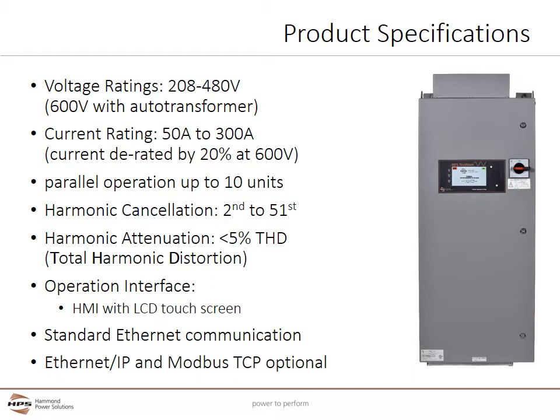The HPS TrueWave active harmonic filter offers voltage ratings from 208 to 480 volts; 600 volts can be achieved with the addition of an auto transformer. Current rating includes frame sizes from 50 to 300 amps, and up to 10 units can be installed in parallel for applications up to 3000 amps. The TrueWave provides harmonic cancellation from the 2nd through the 51st harmonic, achieving below 5% total harmonic distortion. It features an HMI with an LCD touchscreen, standard Ethernet communications, along with Ethernet IP and Modbus TCP optional communication modules.